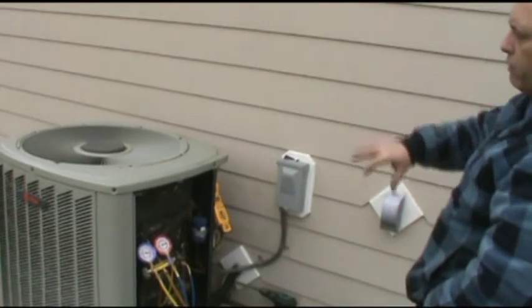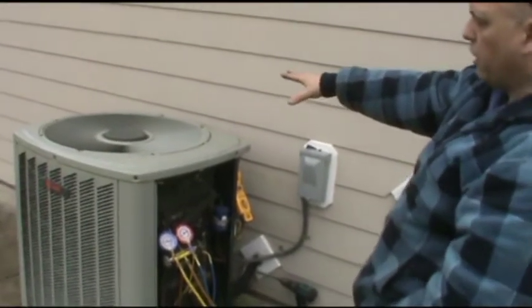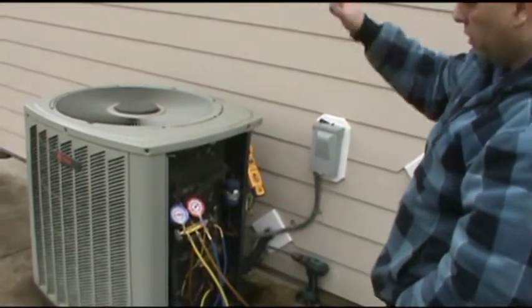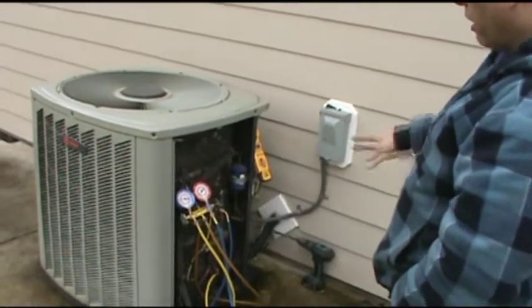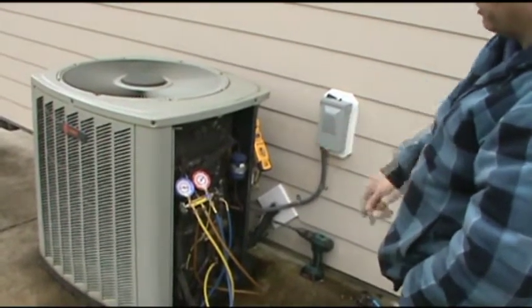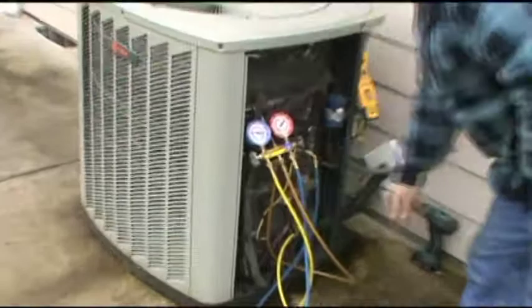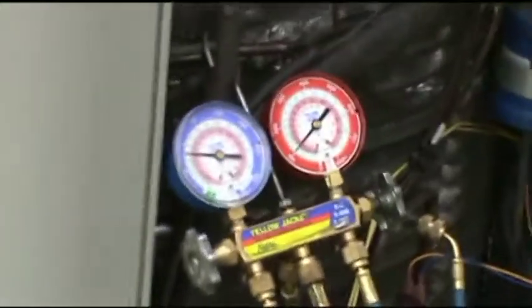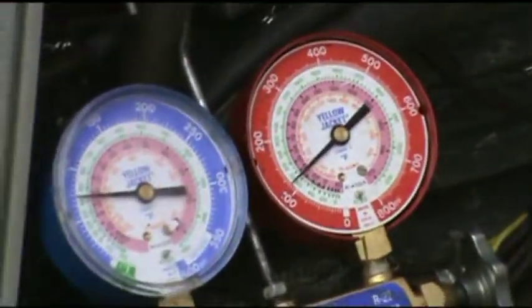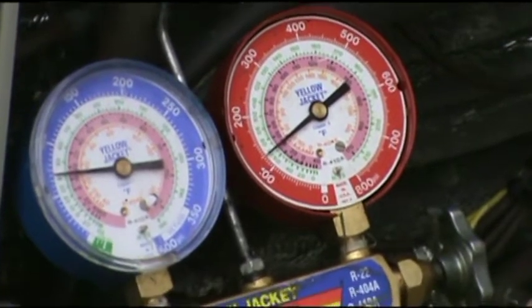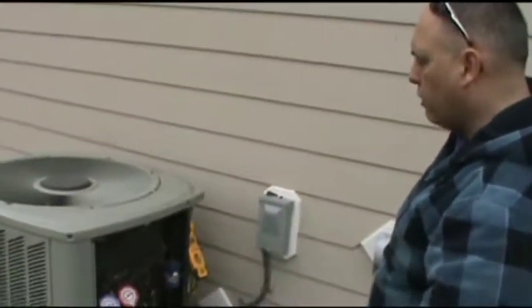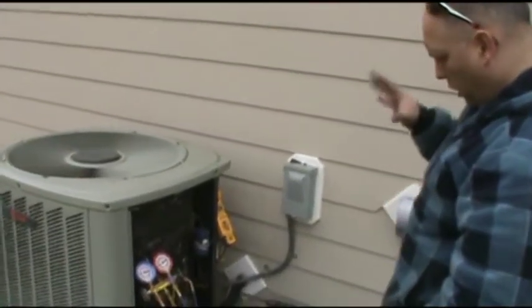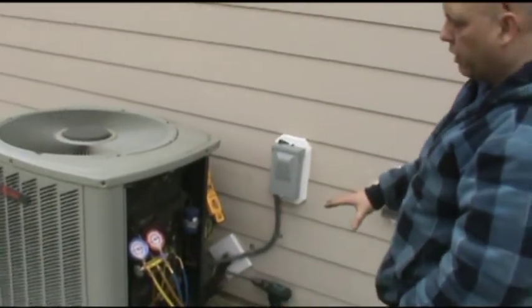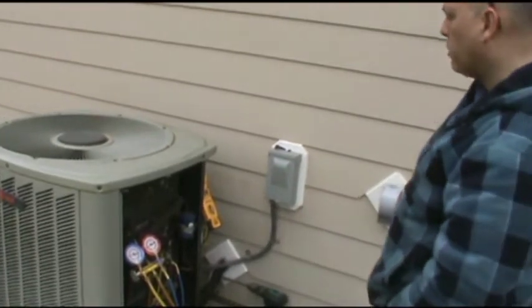The first step of termination is it brings the condenser fan motor back on to lower the head pressure. The next step is it'll switch the reversing valve here, and you hear the small whoosh when it changes. And now we're back into heating mode. Again, the pressures over time will return to where they were before we initiated defrost. So we know we're running good in heating. We know the defrost cycle works correctly.